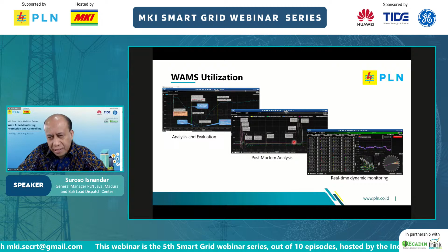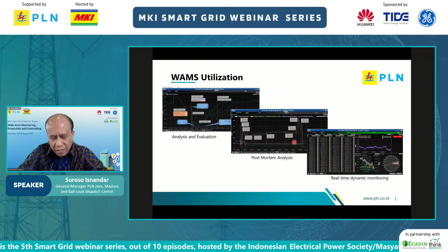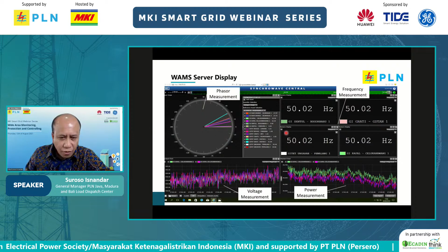For example, the one we provide here is actually a real capture from the previous disturbance in the system. And also, of course, to increase the situational awareness, to access the real-time dynamic monitoring that will assist the dispatcher to monitor power system dynamics and react proportionally in order to keep the system in balance. And from here, we can see the example of the WAMS user interface, either from the phasor measurement, the frequency measurement at different point of the system, also voltage measurement and also power measurement.